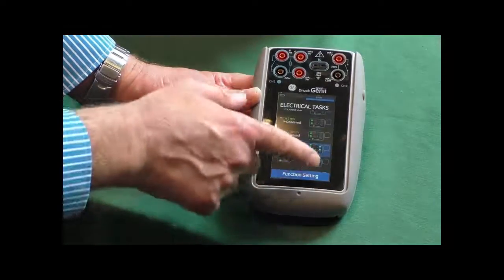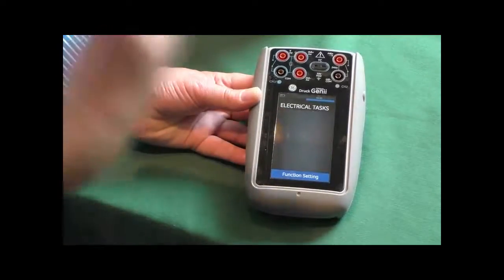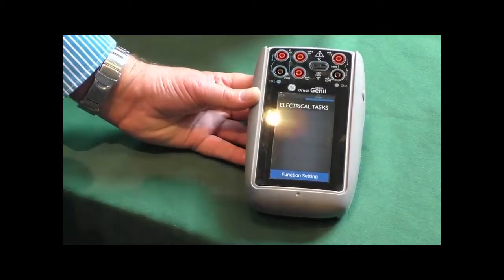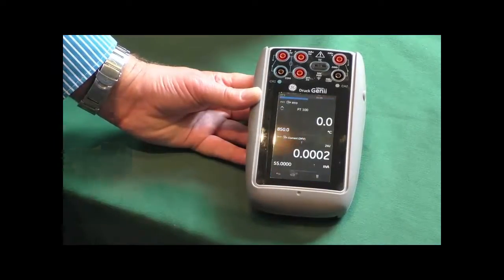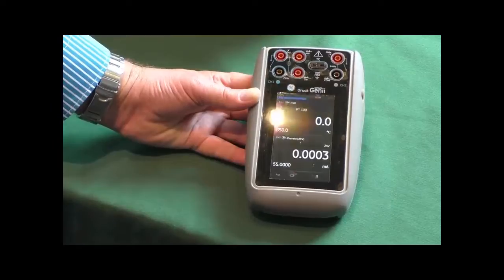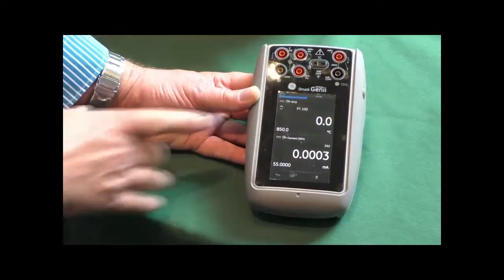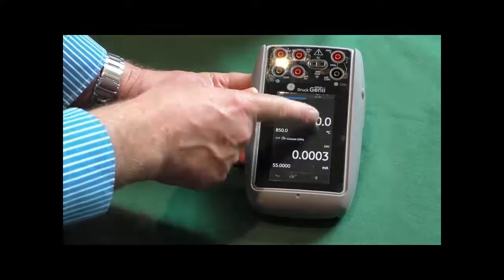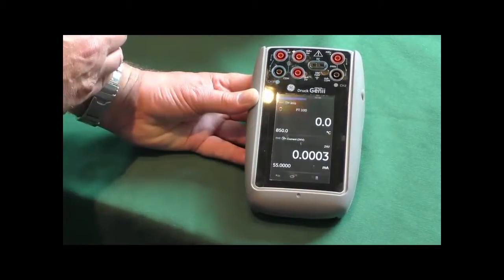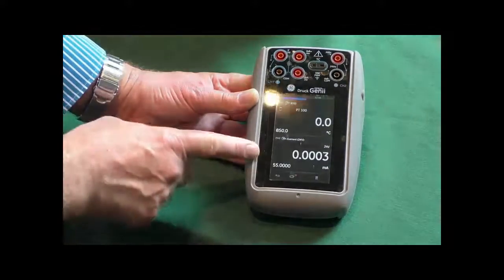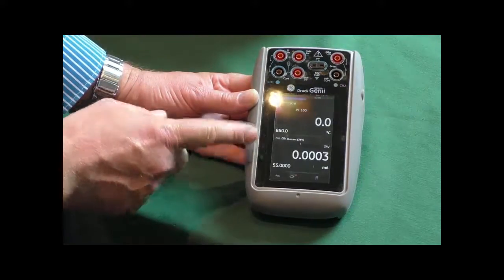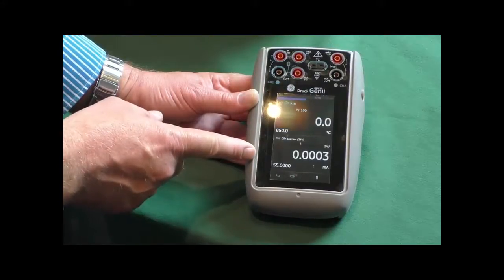We can actually select these as well and put them into our favourites menu. So when you go into your favourites, if they're the tasks that you use quite commonly, then you don't have to go and scroll through all the different tasks. You've just got your favourites already set up. So at the moment it's shown at the top here, we have degrees C. So this is going to be where I'll simulate the RTD resistance into the transmitter. At the bottom here, we have our milliamp output from the transmitter, which I will connect shortly.